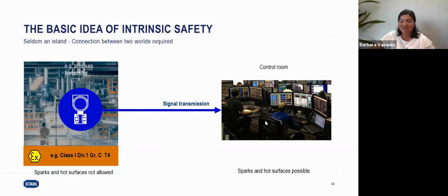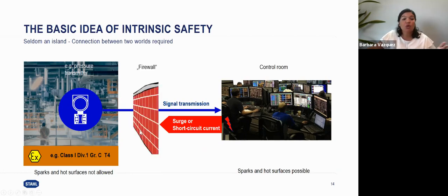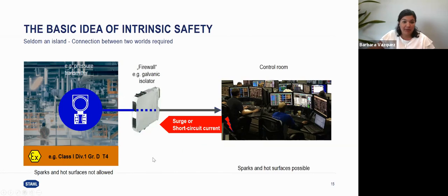that's it, right? Everything will work fine. But in reality, we don't live in an ideal world. So in the safe area, we could have a surge, we could have a short circuit, we could wire it wrong to AC power instead of DC power, or something like that. By having this physical layer connecting the hazardous area to the safe area, we have a path for high energy, which is risky. So we need to put something like a firewall, something that will analyze what wants to pass into the hazardous area and decide yes or no. And that's exactly what a barrier does.